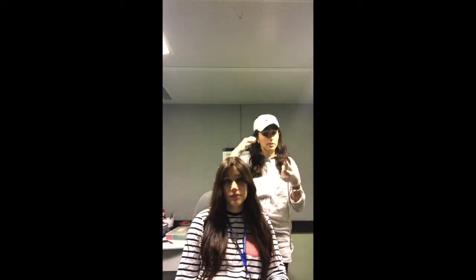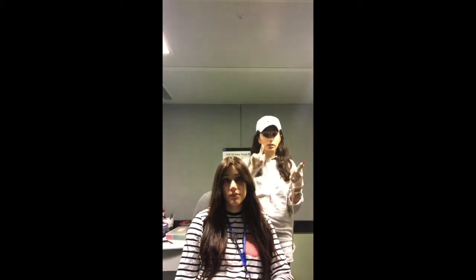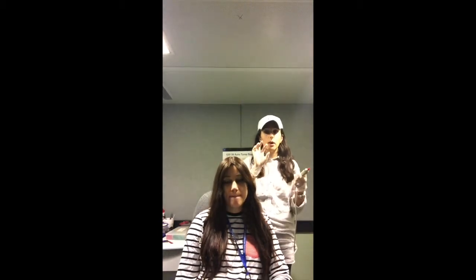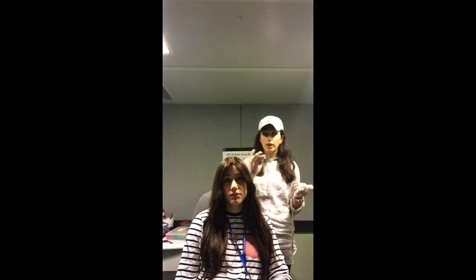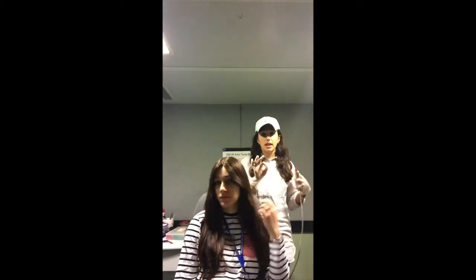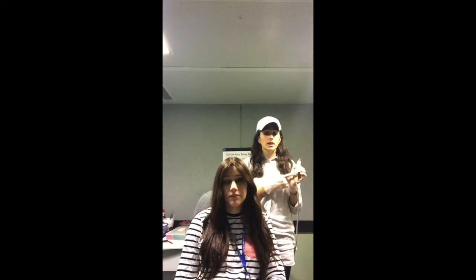You're going to gently pull the ear back, place the probe tip in, and when you see a steady green light, it means you've obtained an airtight seal. That airtight seal is important in order to obtain the information that you need. If you see orange, it means there's no airtight seal, there's a pressure leak, so take it out, readjust, and put it back in to obtain that airtight seal. If there's a yellow light, it means the probe tip is occluded. Take it out, see what's going on, fix it, and start again.